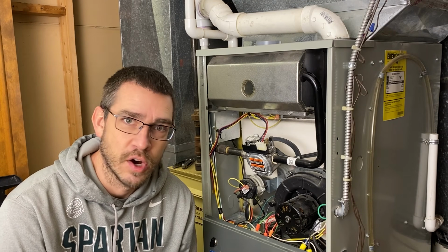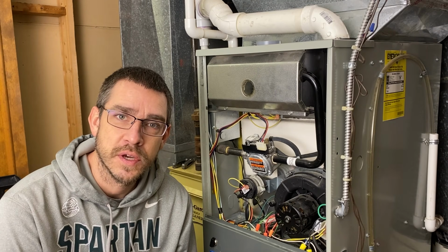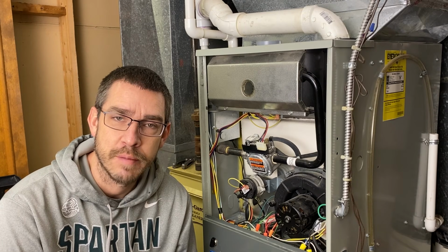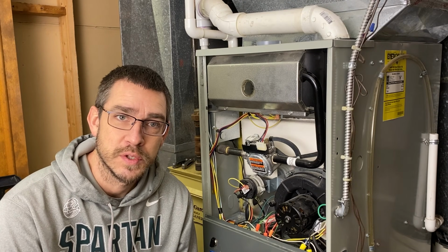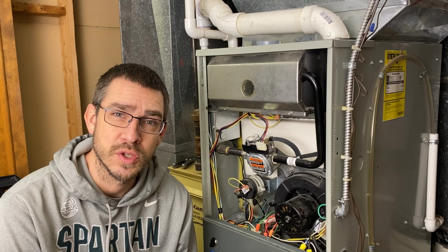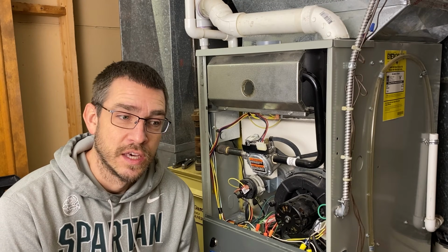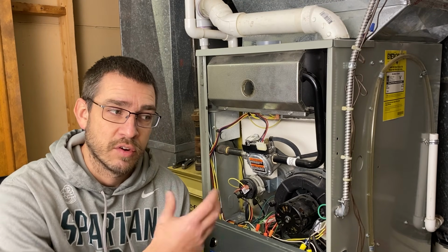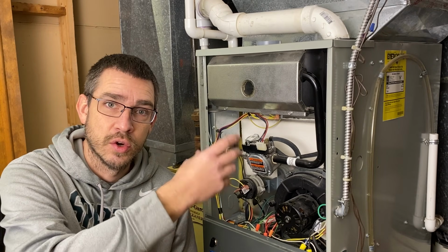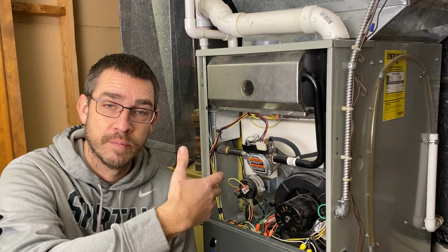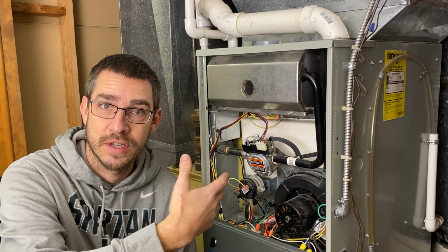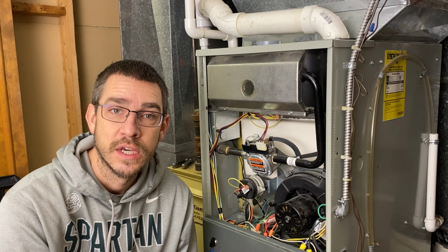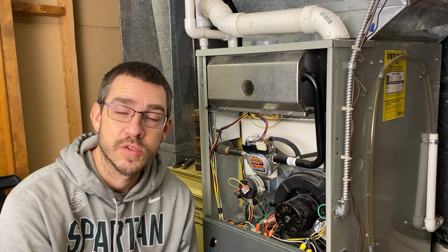There are obviously lots of other things that can go wrong with the furnace, but these are some of the simple things. These are some of the most common things that happen. And so the trouble code on the furnace itself will usually tell you exactly what's going on, or at least give you some hints. And if you understand the checks that it goes through as the furnace starts up, you can usually just watch what happens and see what the problem is. So you can use a little bit of logic to help figure that out.